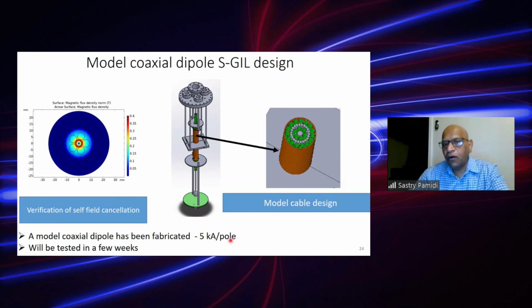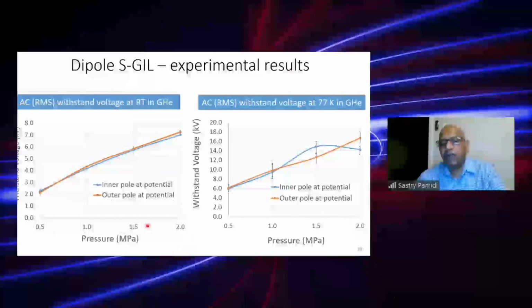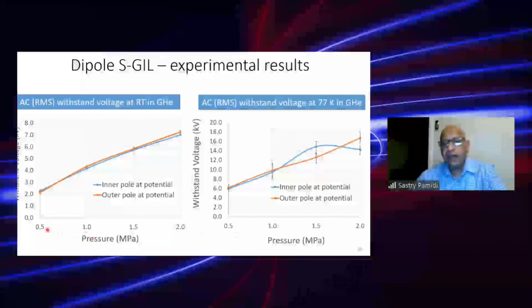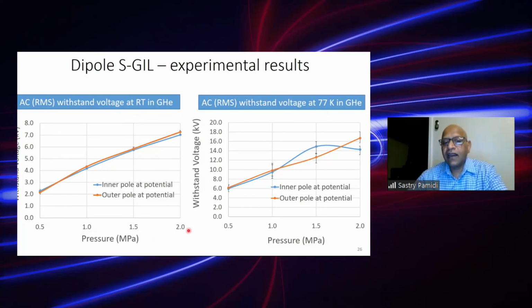5 kiloamps per pole, and we tested it. You see, this is the central one, and then you see the outer cable in the picture. So that is the central cable, and these are insulation rings, and then the outer cable. In helium, when we work with gas, pressure is directly related to dielectric strength. So we test at different pressures, and the maximum we go to is 2 megapascals.